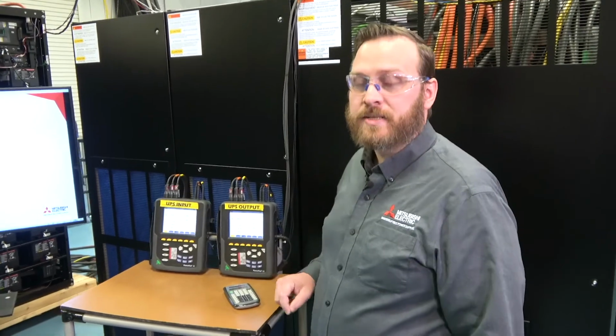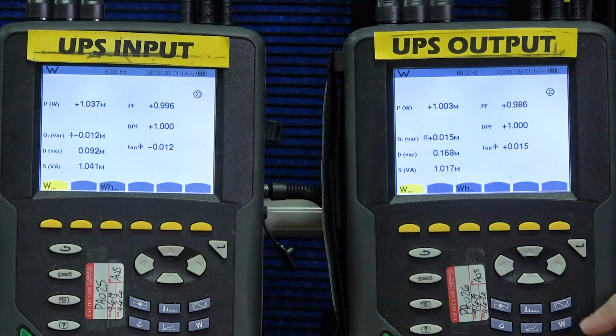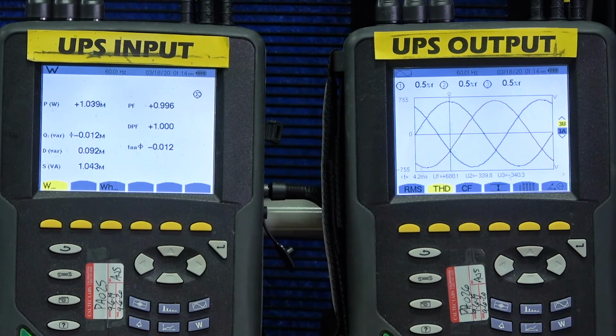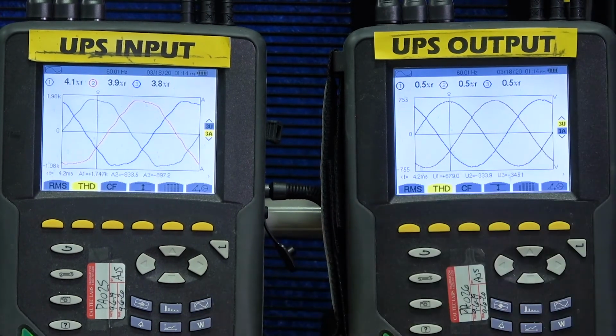Next, we're going to increase our load up to 1 megawatt, or 50% of the UPS. Again, it's interesting to see the harmonic content of the output voltage waveform, very stable at about 0.5% harmonic THD on the output. And our input current harmonics are now down to about 4%. And we'll continue to see that decline as the UPS loads up to 100% output load.